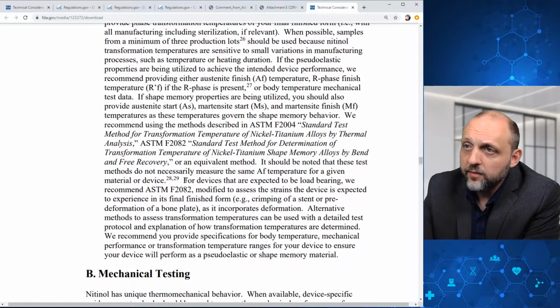And here, FDA specifically calls out that for devices that are expected to be load-bearing, FDA recommends that ASTM F2082 be modified to assess the strain the device is expected to experience in its final finished form as it incorporates deformation. And here they call out alternative methods to assess transformation temperatures can be used with a detailed test protocol and explanation of how transformation temperatures are determined.